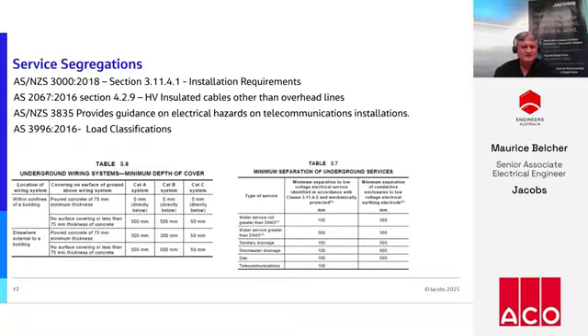Now I'd like to address the segregation issues. There are key tables within AS3000 that we need to reference and comply with, in section 3.11.4.1. Table 3.6 covers the depth of segregation between services, and the table on the right covers horizontal separation between various services. That's certainly the starting point to ensure compliance.